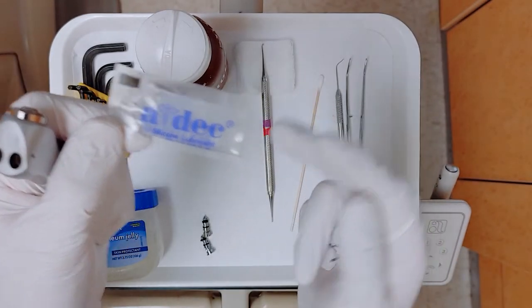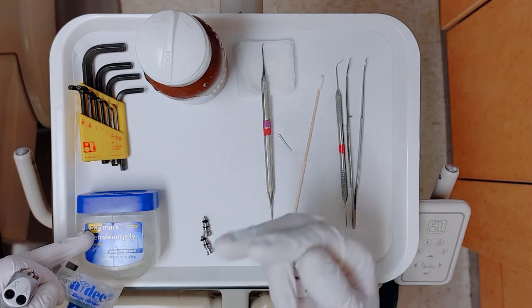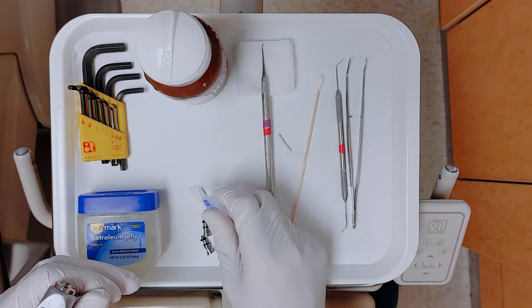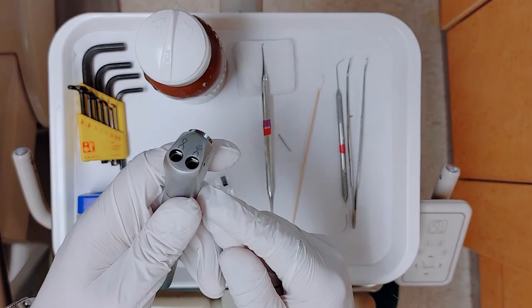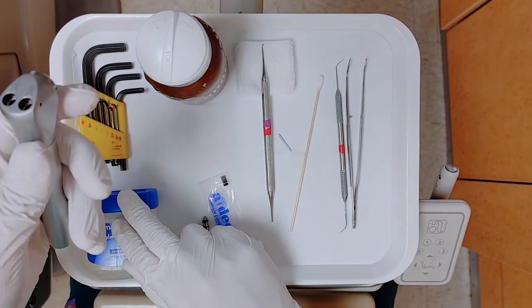If in a pinch you don't have any of this but you're going to order and get some soon, another thing that we can use is petroleum jelly. But don't use it for too long—it is known to eat away at the O-rings. So if you're going to replace the whole unit eventually or soon enough and you just need to get by, you can use that.